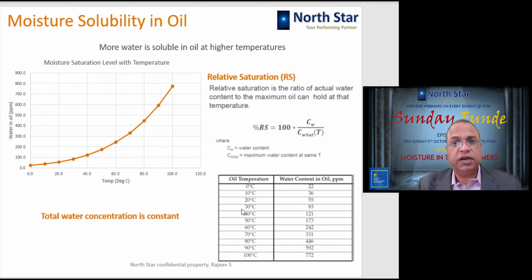Then there is another factor called relative saturation. Relative saturation depends upon the temperature, and it is other than the ppm. Here, this is a typical graph of moisture saturation level in the transformer. Point to be noted here, in that transformer the water concentration is kept constant, meaning, as I said earlier, no water is removed and no extra water is added. The total water, say if 10 liters of water is there, it is still 10 liters in the system, but the temperature is being changed. So if the temperature is changed, the saturation in the oil will vary.